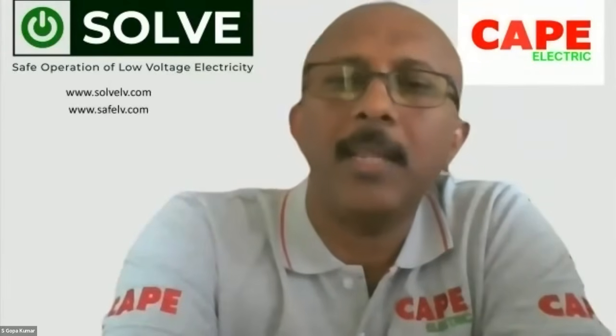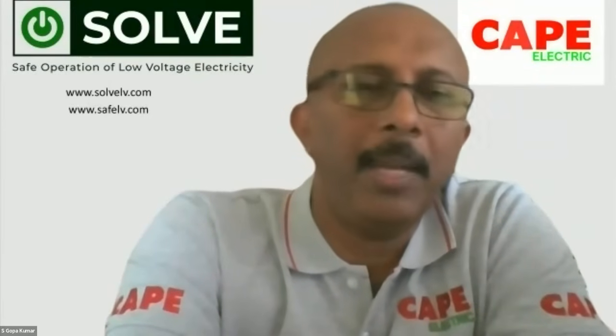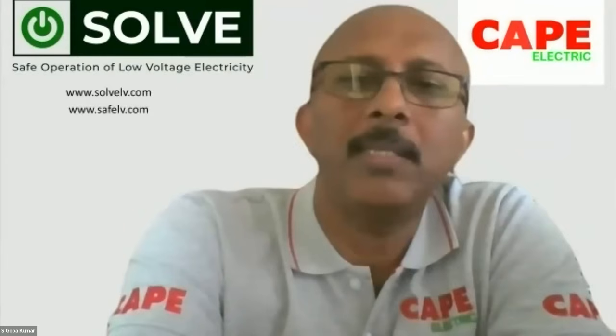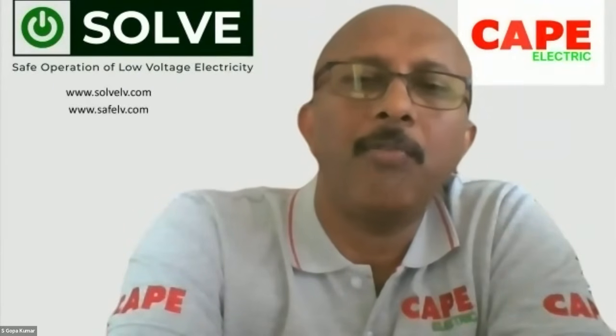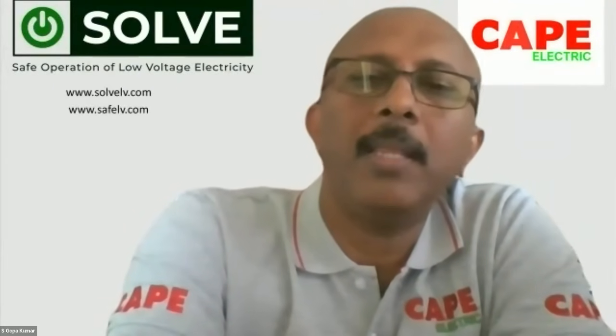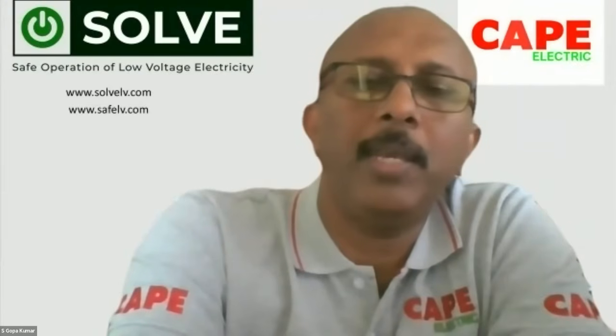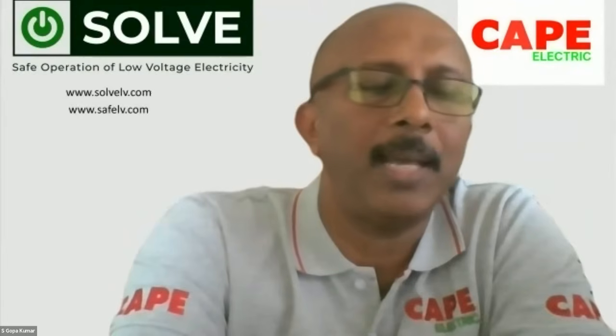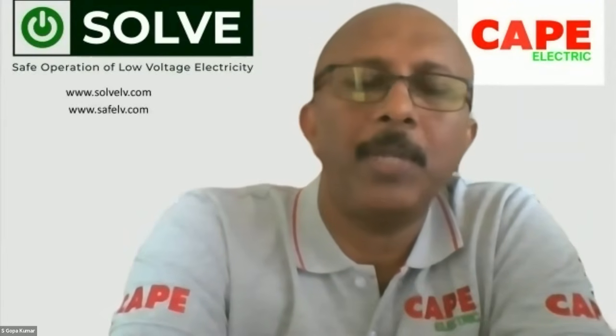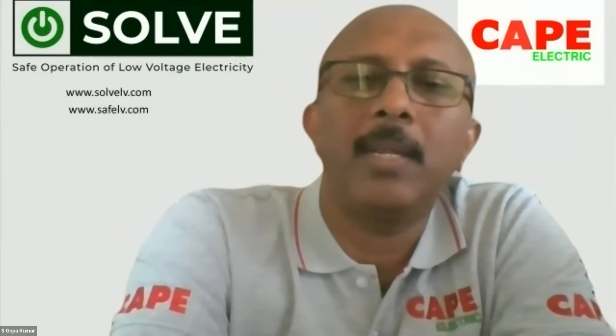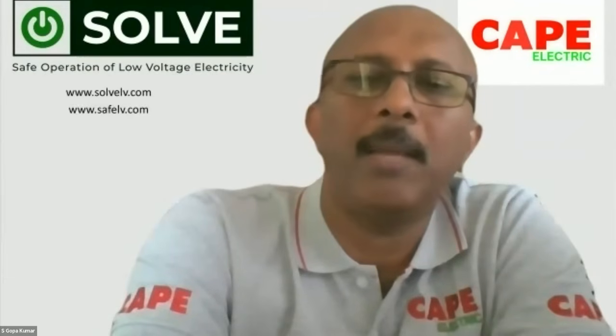You should understand that the RCCB of 30 milliampere will protect only against earth leakage or earth fault. Most of the time, the items which we plug into the extension board are class 2 equipment, say, for example, mobile chargers or sometimes laptop chargers. They are class 2. The RCCB is of no use in that particular case.